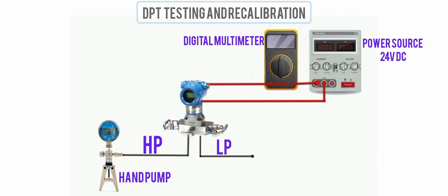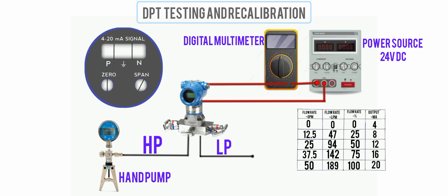We perform the actual calibration using the zero and span adjustments on the transmitter. Apply the zero percent input pressure value, which for us is zero inches water column, to the transmitter and adjust the zero until we get an output current of 4 milliamps.